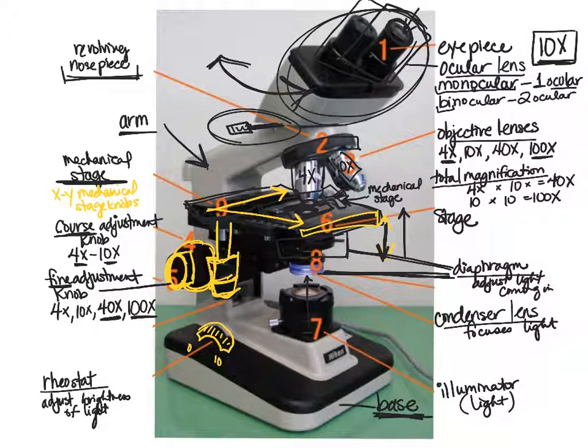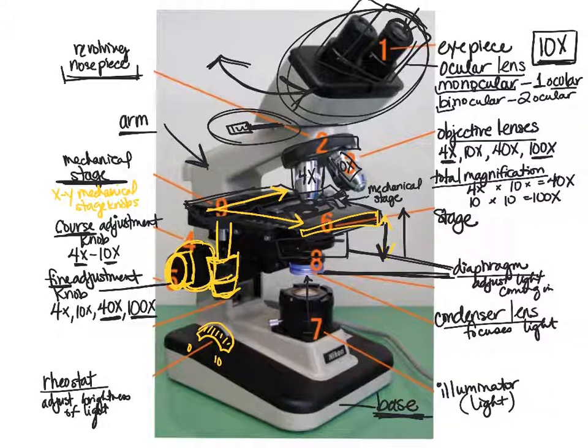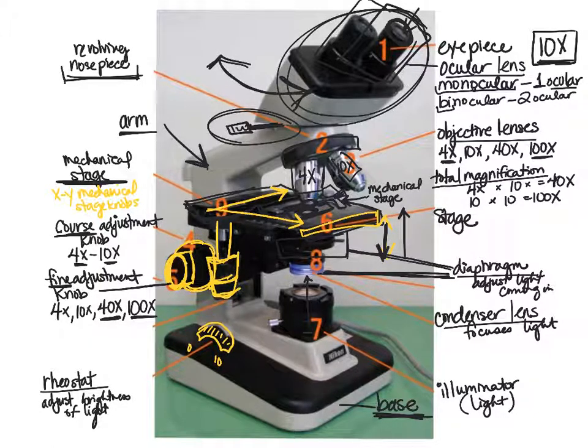Now let's discuss immersion oil. When light moves from glass to air to glass again, there are differences in refractive indices between the two media, and we lose some resolution. As we get to higher magnifications, we can lose more and more resolution. We get around these different refractive indices by using oil immersion. Our 100x lens is our oil immersion lens.